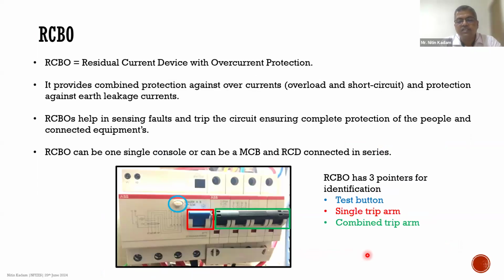We also have a device called an RCBO, or residual current device with overcurrent protection, which is actually an integrated MCB and an RCD together. In this case, if you see here on this side, you have the residual current device, and this side you have the MCB. So this is C25, so type C MCB with a rated current value of 25 amps. You have a test button for the RCD, a single trip arm for the RCD, and a combined trip arm for the MCB. So this is also a combination that can be used, and we'll see what kind of devices are to be used for what kind of earthing network that is available at the building sites.